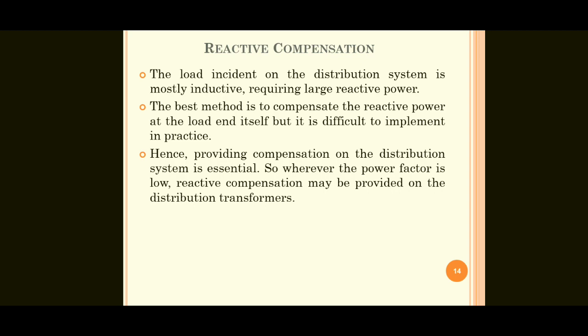Next one, the best method is to compensate the reactive power at the load end itself, but it is difficult to implement in practice. It is not so easy to compensate the reactive power at the load end. Some shunt devices, meaning STATCOM devices, are placed to compensate this reactive power at the load side. The procedure is entirely different. It is very difficult also, and the compensation is a very tough task. So by using FACTS devices, compensate the reactive power at the end of the load side. So STATCOM devices are placed at the end side.